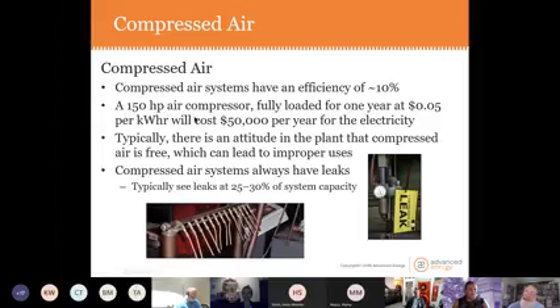Just one data point, if you have a 150 horsepower air compressor running fully loaded and you pay about 5 cents per kilowatt hour, it'll cost you about $50,000 a year for the electricity just to run that 150 horsepower compressor. And if you have a 10 or 20% leak rate of your air, you can see that you're compressing 20% of this. So $10,000 a year is going to just make leaks. And that's terrible. And that's in every single plant. And typically there's an attitude among people in plants that, open this valve, there's compressed air. It must be free. It's just there. It's everywhere in the plant, anywhere I want it. But it is not free.